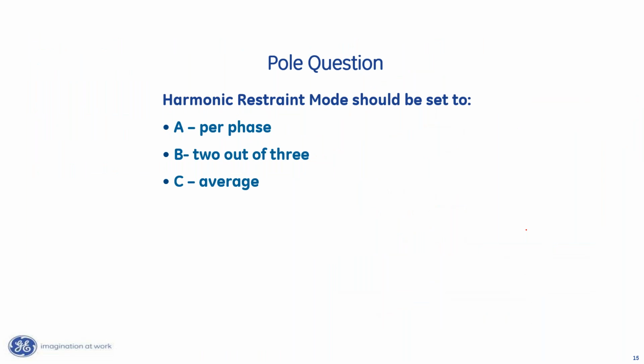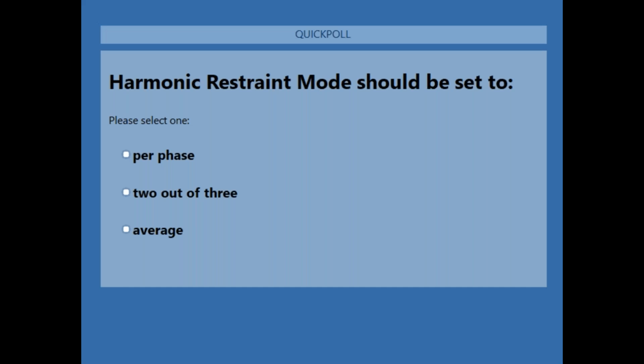Now, inside of most microprocessor-based relays, certainly the T60, T35, 745, as well as the 845, we have the ability to set an inhibit mode or harmonic restraint mode. And so our options on that harmonic restraint mode are we can set it per phase, like the electromechanical relays. We can set it on average, or we can set it at 2 out of 3. So the poll question that John's going to open now is, how should I set it?